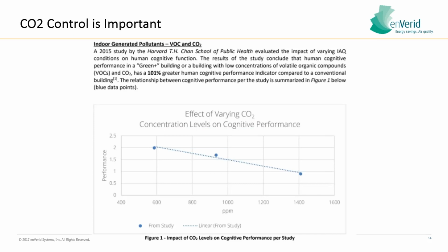The other is that CO2 matters in the eyes of many studies that are coming out right now. We may all be familiar with the studies from the Navy and others that say CO2 is not harmful to your health within a pretty extreme range. There's an OSHA study that says you can get up to 5,000 ppm without CO2 impacting your health negatively. However, there's more and more studies coming from Harvard, from University of Wisconsin, Europe, other places, that while CO2 at elevated levels might not be harmful to health, it definitely impacts cognitive function at very low levels. So you can see here that between 600 and 1400 ppm of CO2, there's a pretty drastic change in cognitive performance. So that's something that enVerid does remove. enVerid solution does remove CO2.